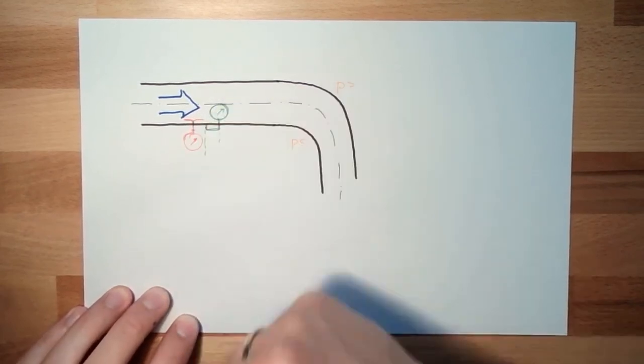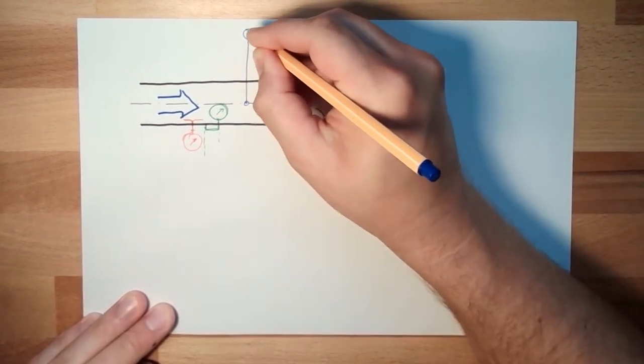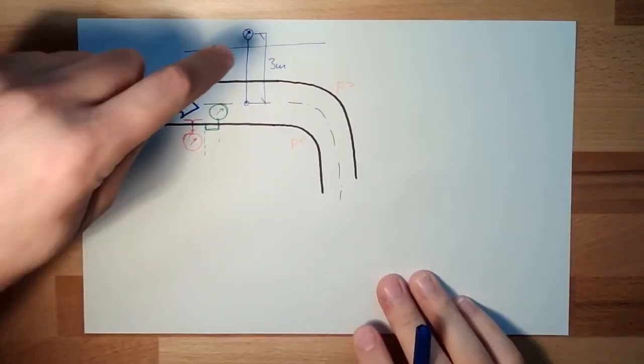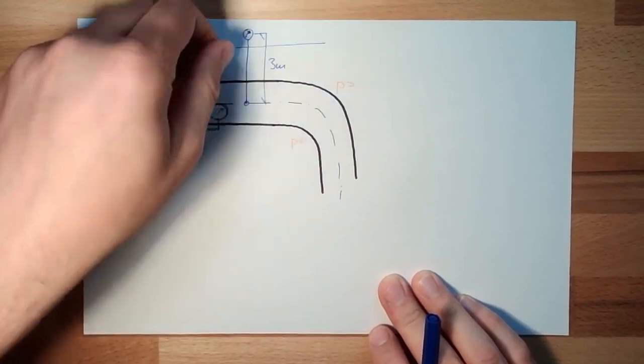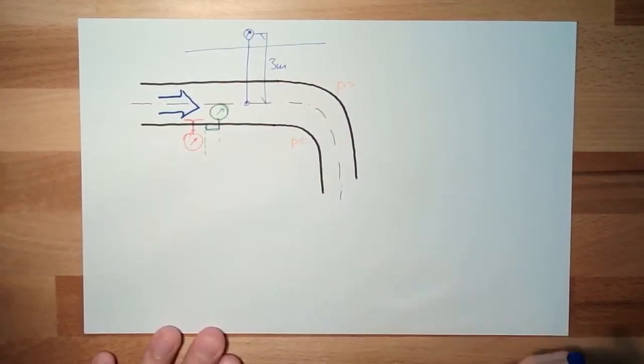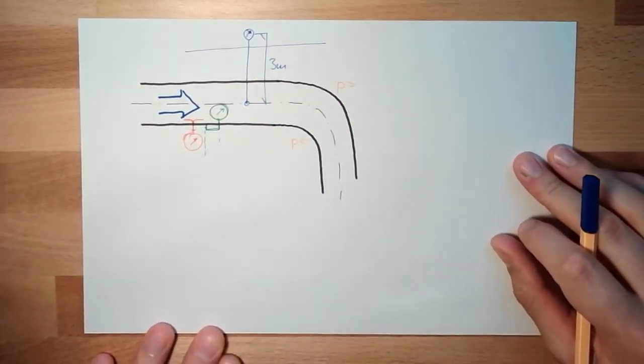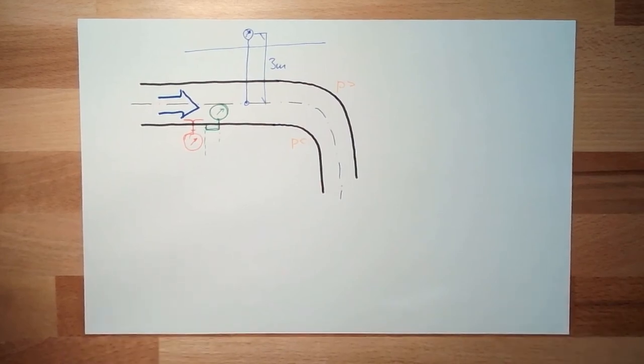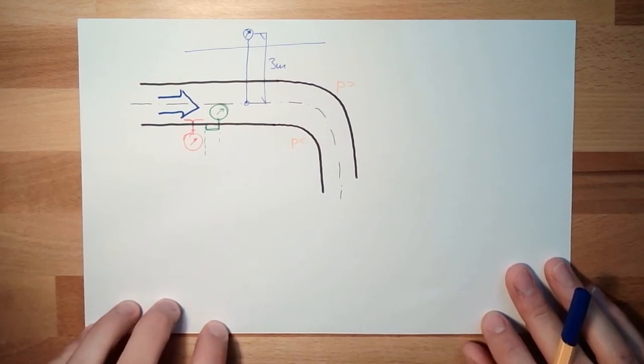You also have to take care of where your sensor is located relative to the measurement point. If the measurement is here and you go up to the next floor — say a difference of three meters — you measure less pressure up there, because there is a liquid-filled part of the tube which has some mass and applies force. You have to know where to place the pressure measurement device and account for height differences. You also have to think about heat: if this is steam, heat might influence the measurement a lot, so the sensor must be placed far enough from the steam source.